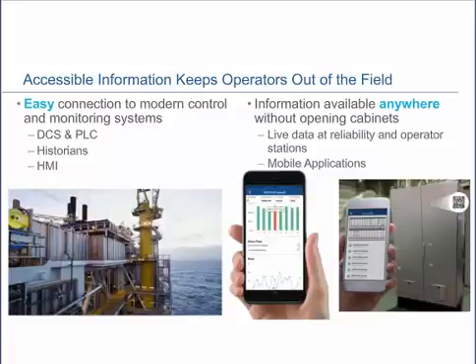Again, this is OPC UA, so this is the latest OPC offering. It is for reading data, and so it is a one-way communication. So no one is going to be able to go in and change configurations using OPC. But you're able to pull that data out by browsing that OPC server and looking for the tags, which in this case would probably be the main value tags for each of your channels that you're wanting to see.